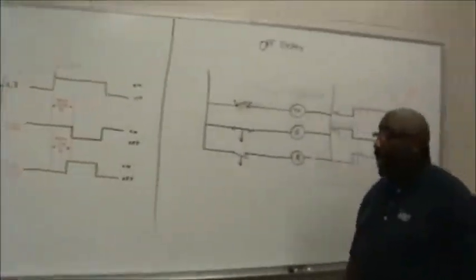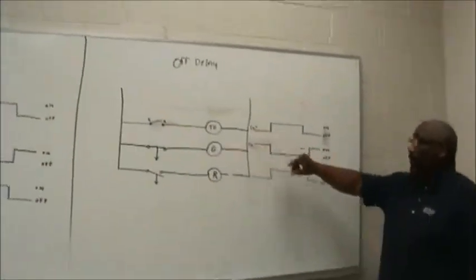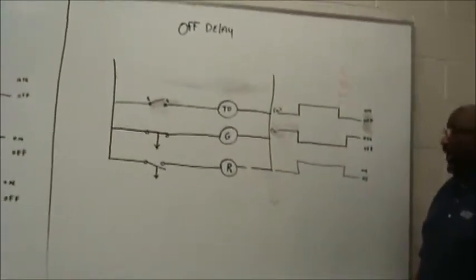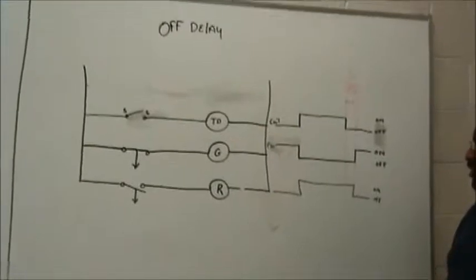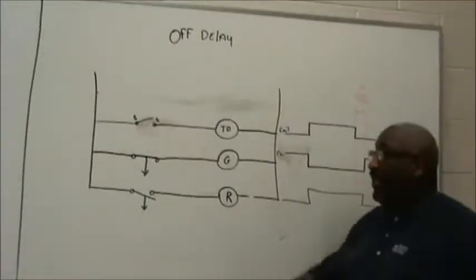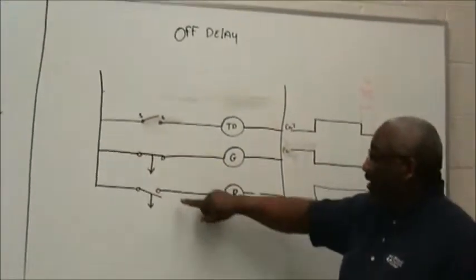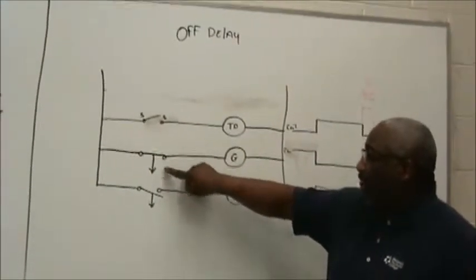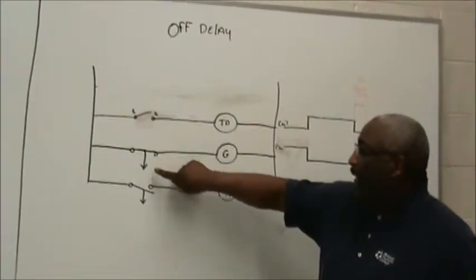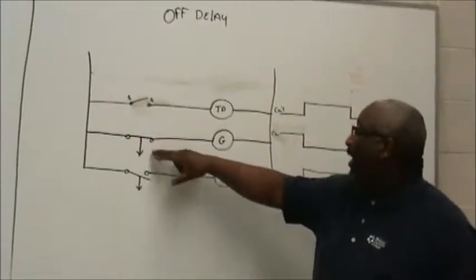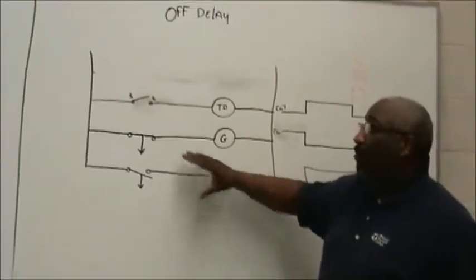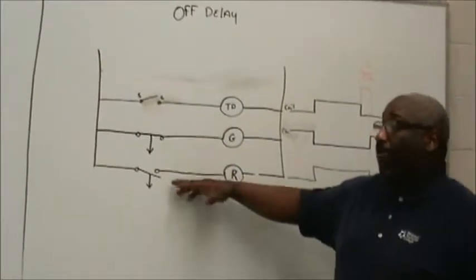Now next, I want to move to the off-delay. The off-delay timer has what we call instantaneous contacts. I have the exact same setup, with the exception I'm using an off-delay timer because the arrow is pointing down, which is different from the on-delay. That's how you tell whether you're working with an on-delay or off-delay timer.